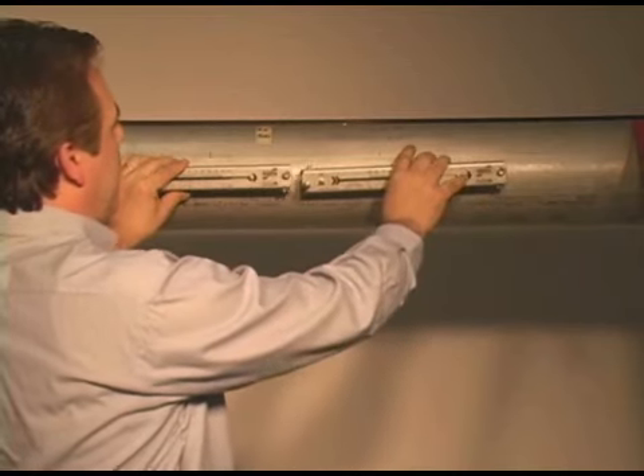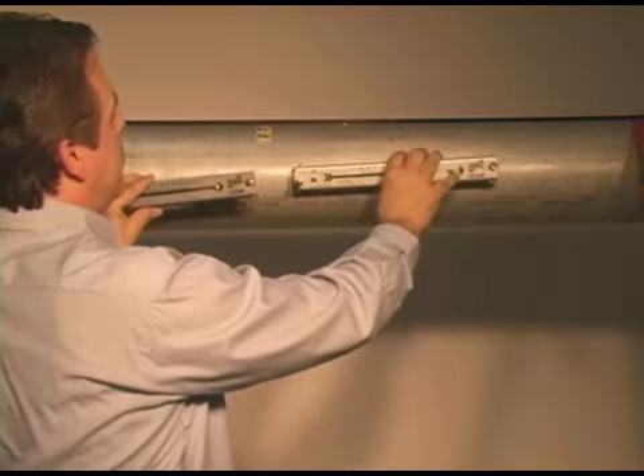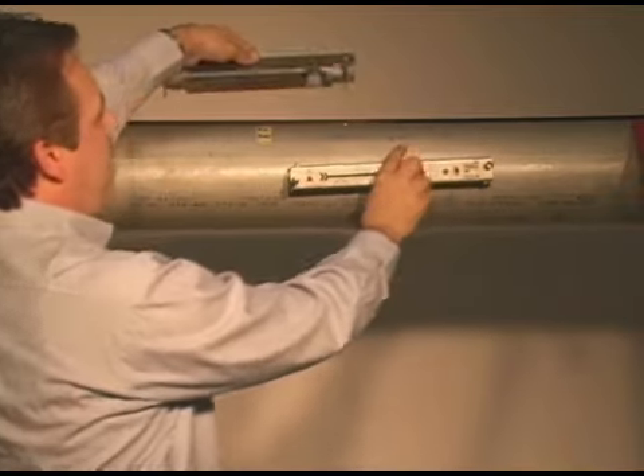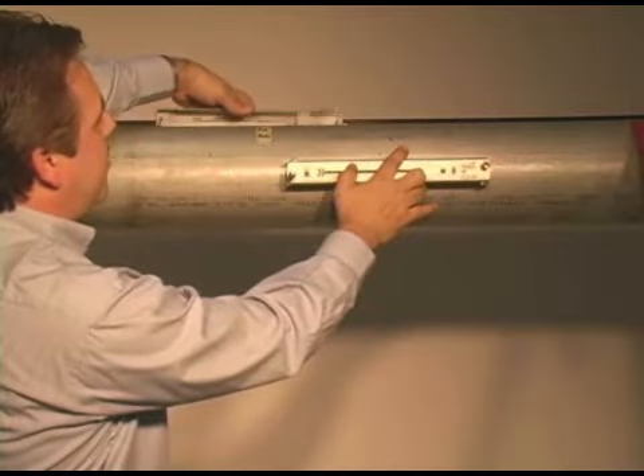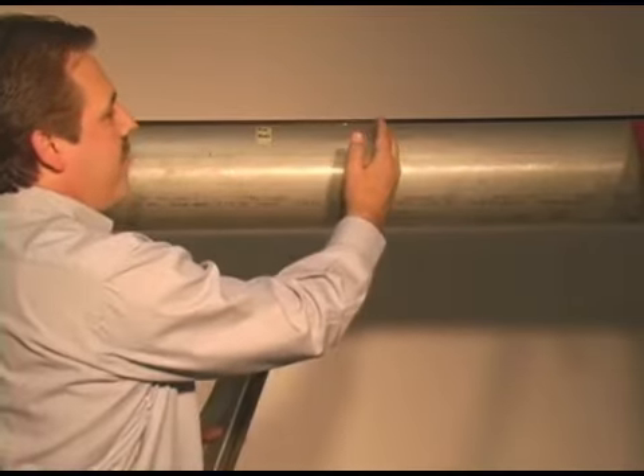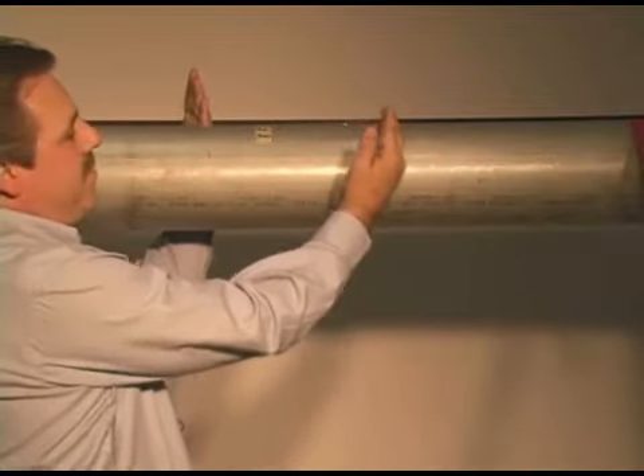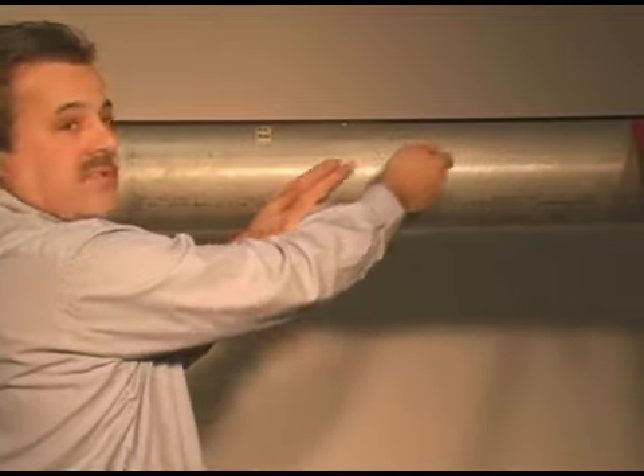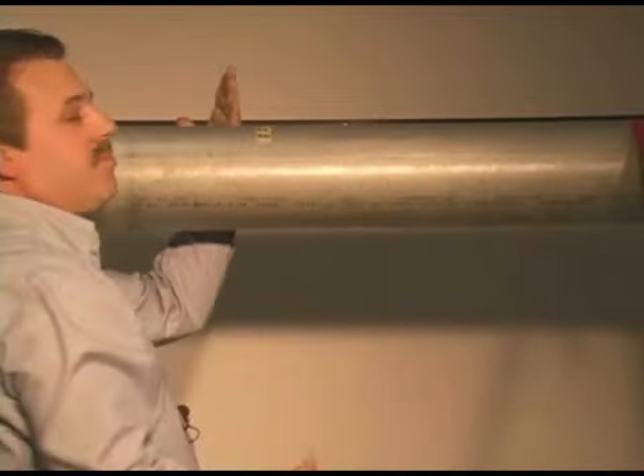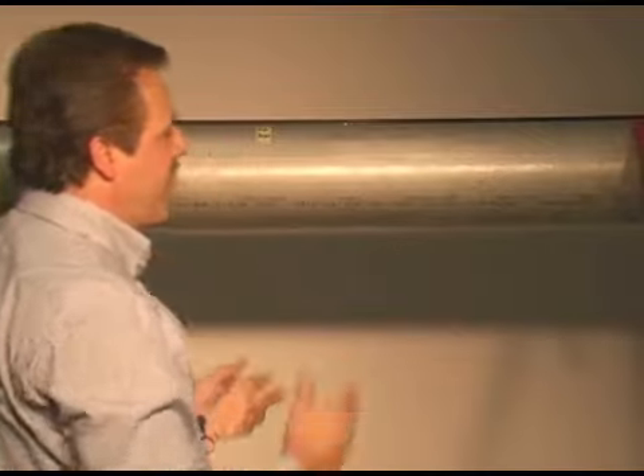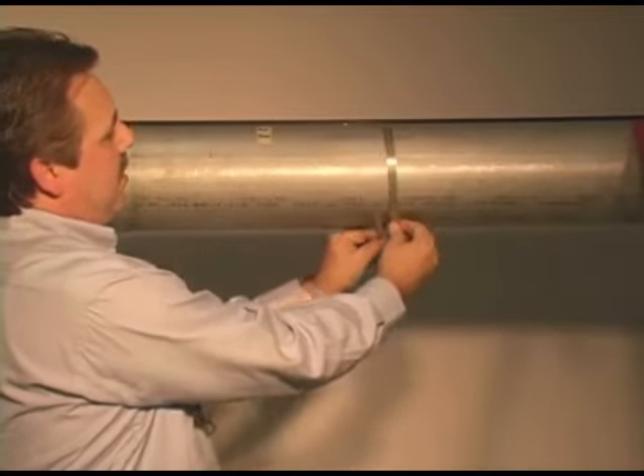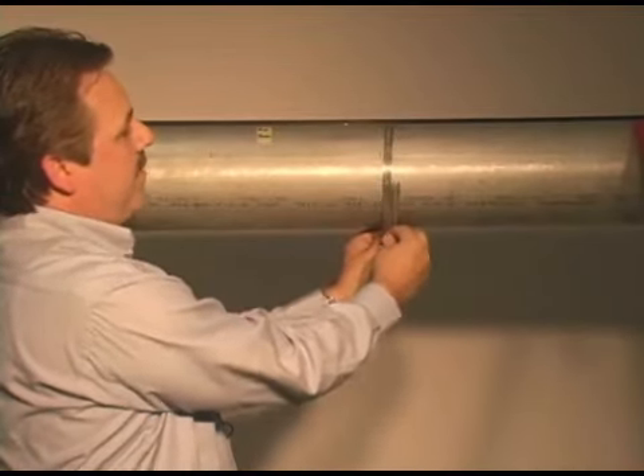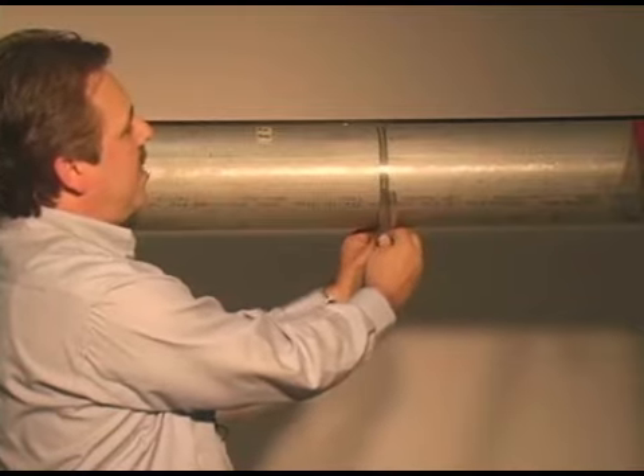That would be true also if you decided you had to change to a single sound path, where your other track is now going to be on the opposite side of the pipe. You'd have to get a little bit creative to measure your 10-inch distance from here to the other side of the pipe. You could use a flange, if there's a flange nearby, to measure your point from here to here. You could use a straight edge, something like the strap that we supply to mount the track mount, to measure your distance across.